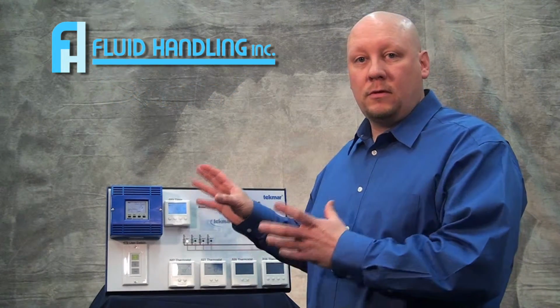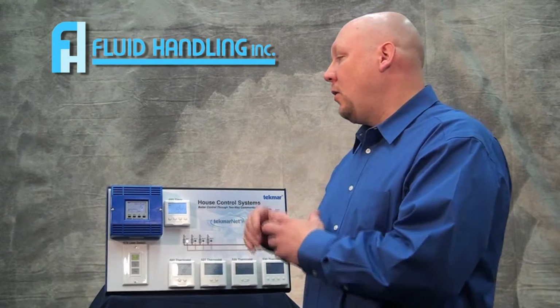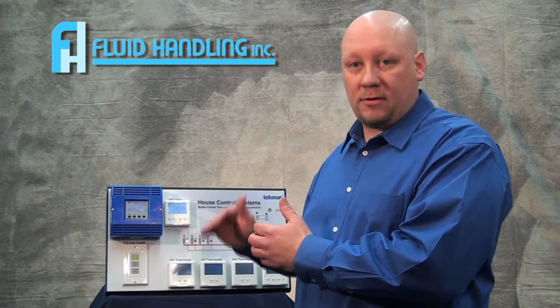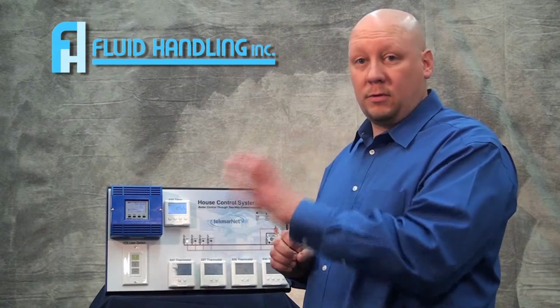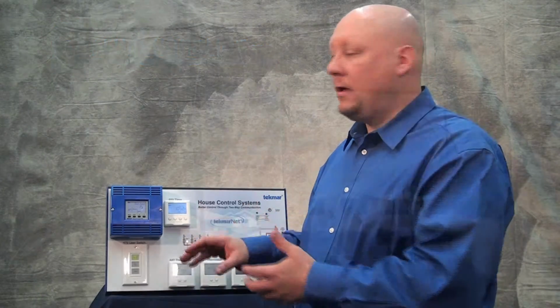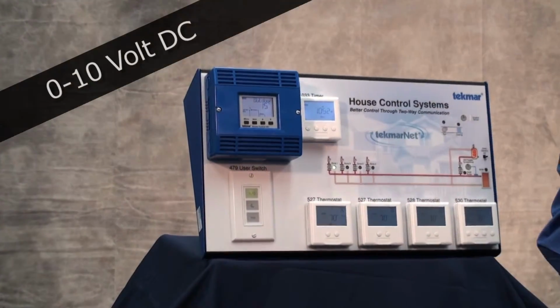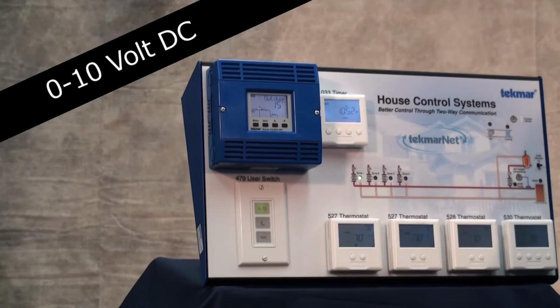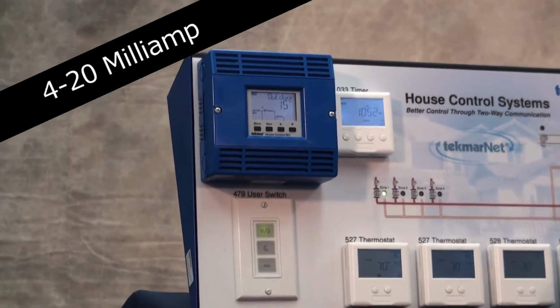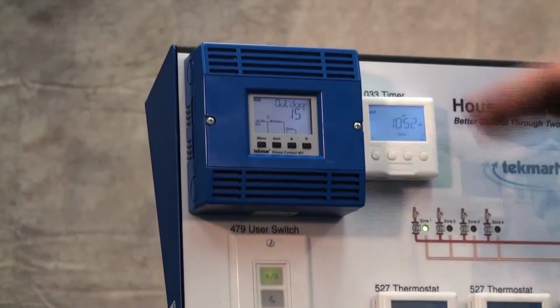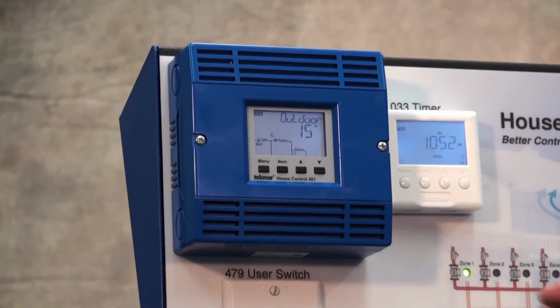With the 400 house control series, what we're doing is, with a ModCon boiler, Tekmar will take over the modulation of the boiler. So you will need to go into your boiler control, tell it to accept an external signal. The Tekmar 400 house control works with either a 0 to 10 volt DC signal or a 4 to 20 milliamp signal. We can tell it in here which one you have.